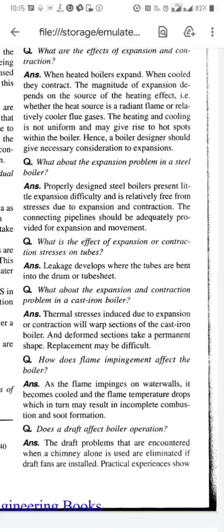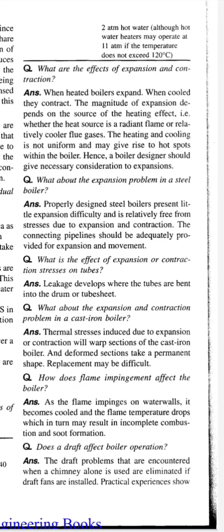The first question: what are the effects of expansion and contraction? Answer: when heated, boilers expand; when cooled, they contract. The magnitude of expansion depends on the source of heating effect, meaning whether the heat source is a radiant flame or relatively cooler flue gases. The heating and cooling is not uniform and may give rise to hot spots within the boiler. Hence, a boiler designer should give necessary consideration to expansion.